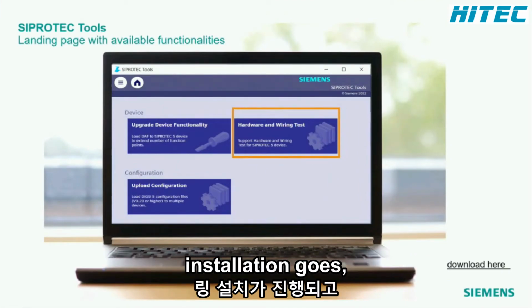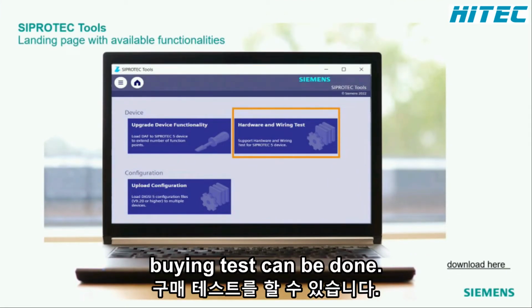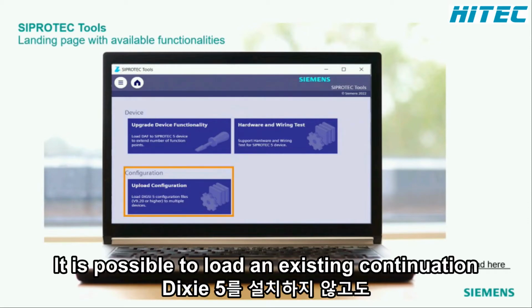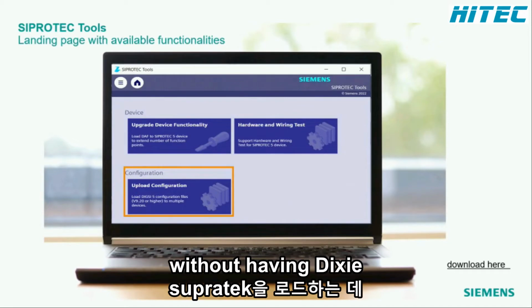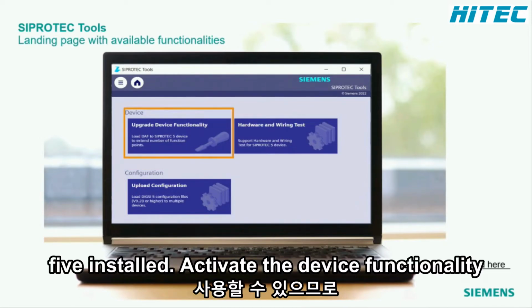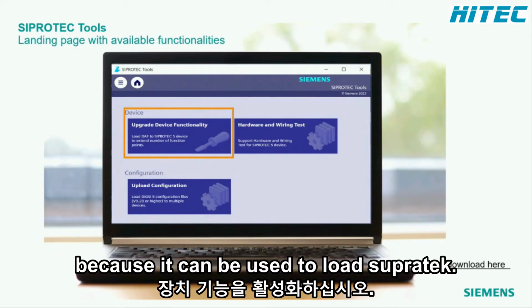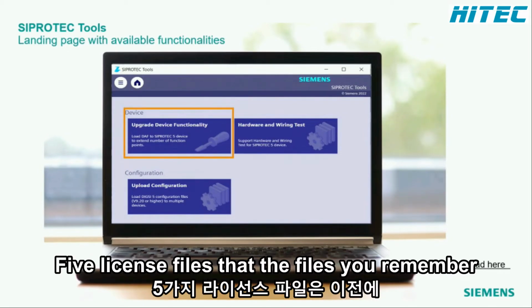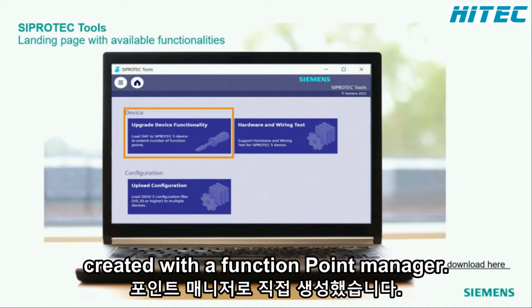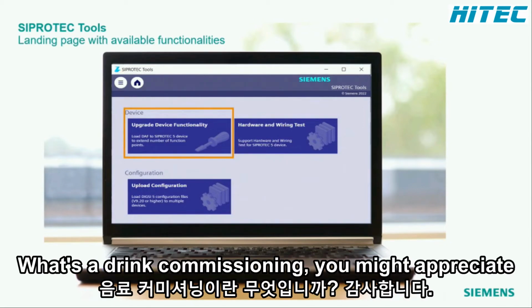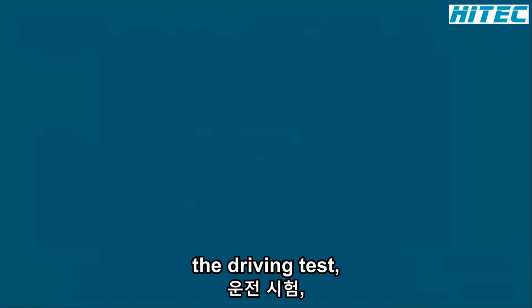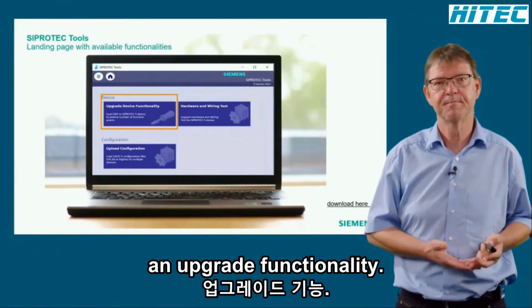During installation, a smooth hardware and cubicle wiring test can be done. It is possible to load an existing configuration into the device without having DIGSI 5 installed. And this tool also allows to upgrade the device functionality because it can be used to load SIPROTEC 5 license files, the DAF files, you remember, which were beforehand created with a function point manager. Also during commissioning, you might appreciate the wiring test and upgrade functionality.